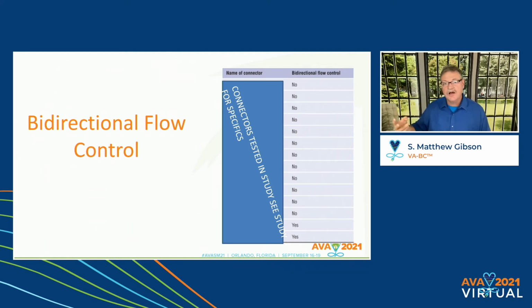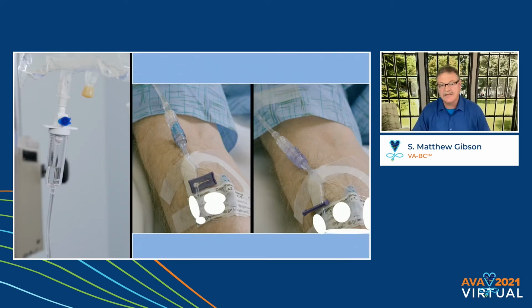There were only 2 of the connectors that I tested that had bi-directional flow control. And again, what that means is your bag goes dry, the pump stops, starts beeping. The patient grabs the bag and holds it at their waist, and they walk to the bathroom. The blood backs up halfway up in the tubing. This ability of the connector will stop that very thing. And there were only 2, and it was the anti-reflux needleless connectors that did, in fact, have this bi-directional flow.